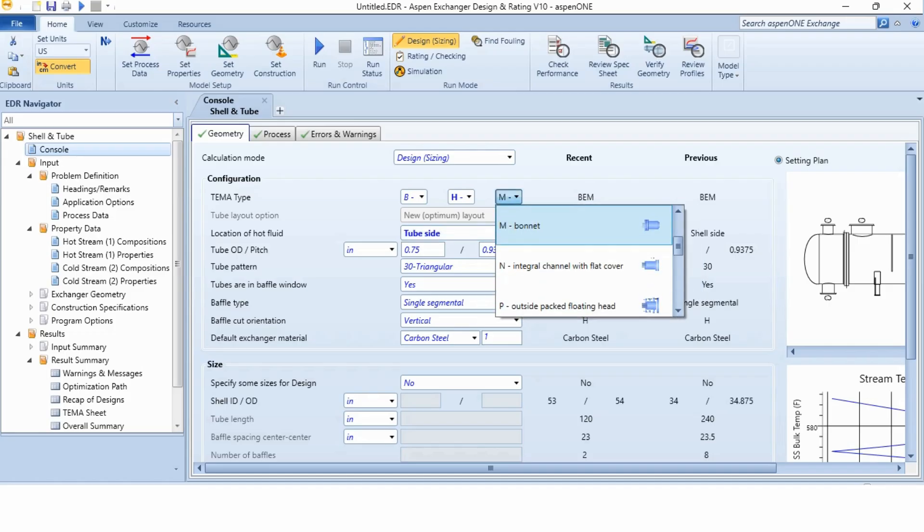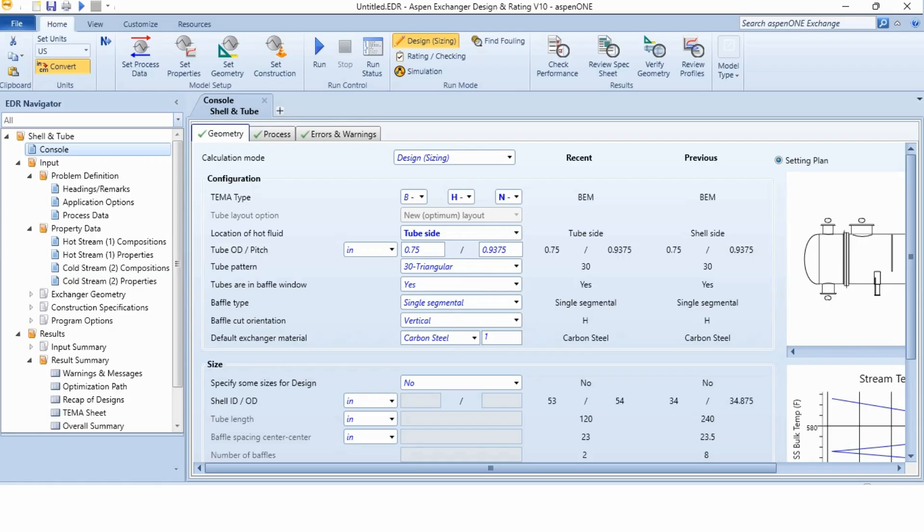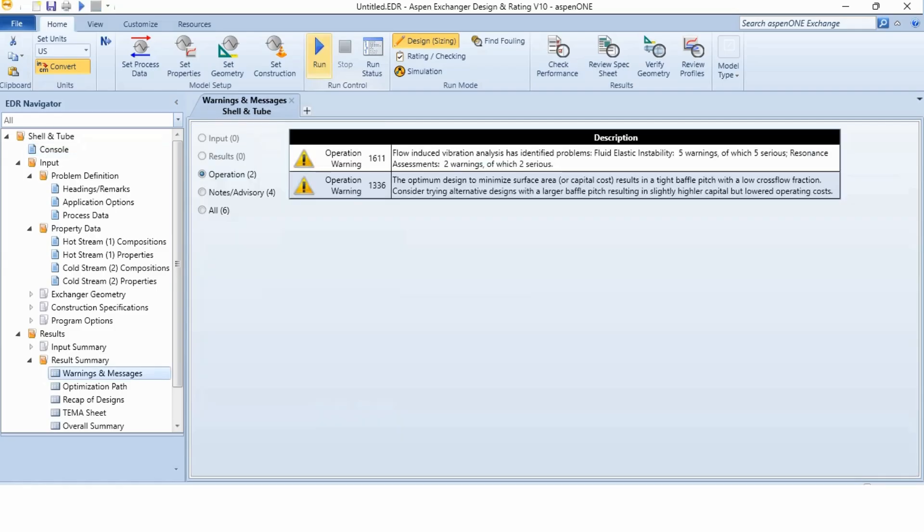The problem is associated with the flow rate. So, we will select it as H. Similarly, in rear head, bonnet is selected. If you select it and you will run it, you will see again Aspen will not give the answer. The correct answer is with N integral channel with flat cover. Similarly, let's first just go to the run and see whether we can get the required results again or not with BHN TEMA. Earlier, it was BEM, now it is BHN.